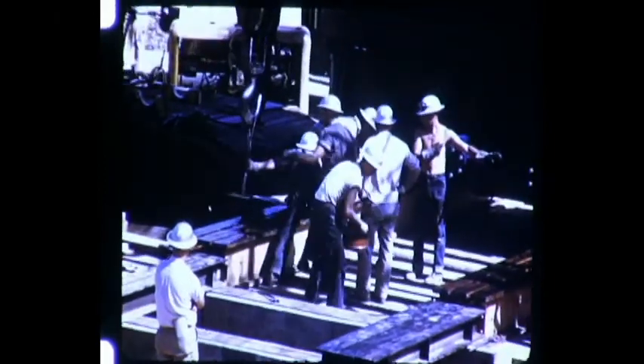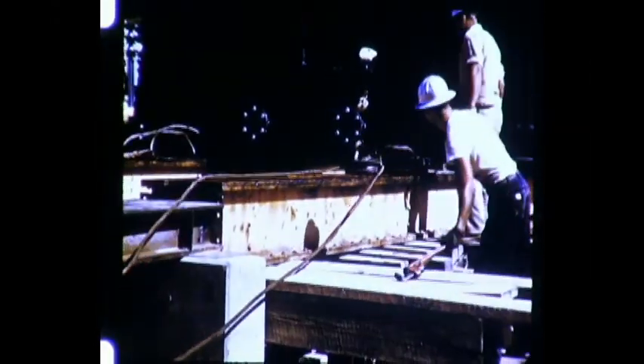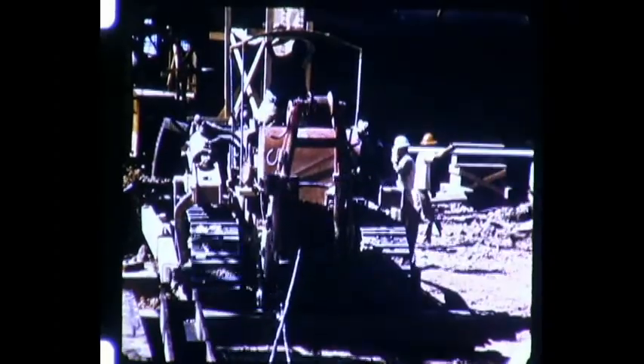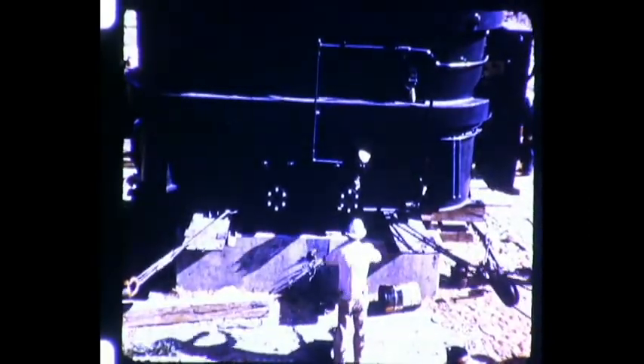Now then, with the skid plates in position, we're almost ready for the move itself. Cables are placed around the sheaves and attached to pulling eyes at the base of the transformer. Cable number 1 to a crane winch is ready. Cable number 2 to a bulldozer winch is ready. And here she comes, upright and steady, with the crane and bulldozer winching the unit easily across the cribbing toward the footings. The foreman watches every move as the transformer slides along the skid beams, signaling the crane and bulldozer operators to keep the pull steady and even.